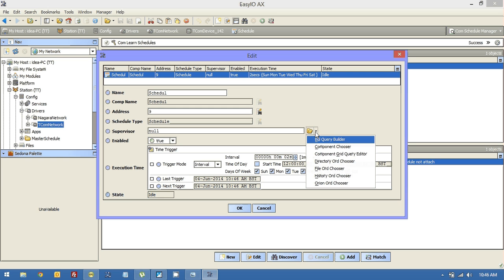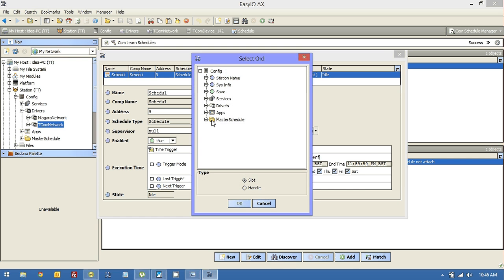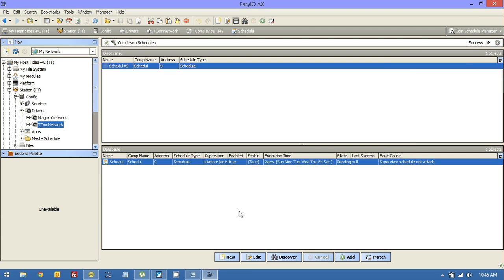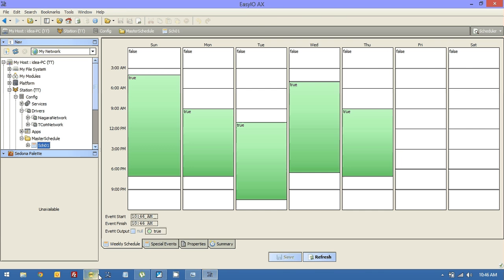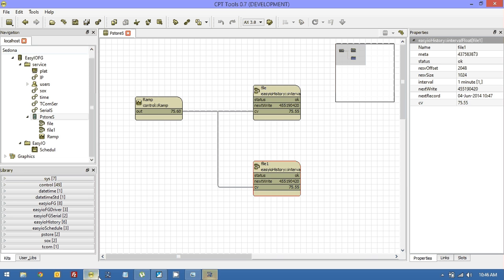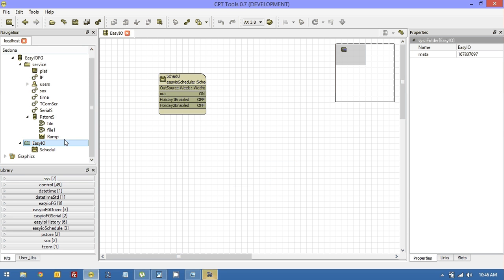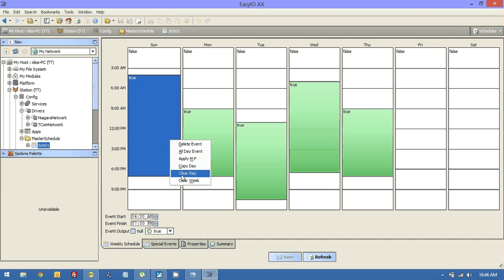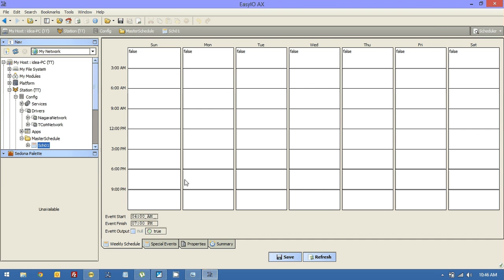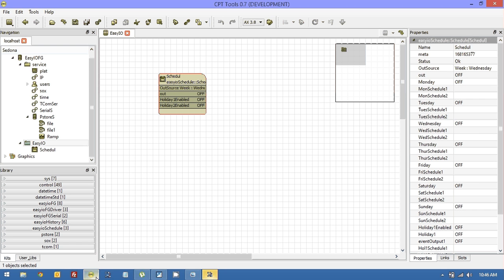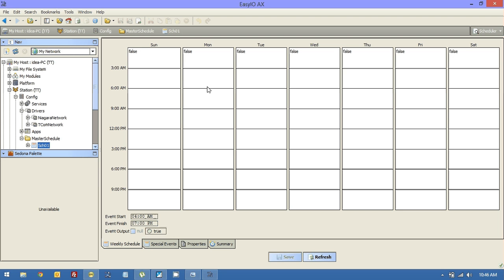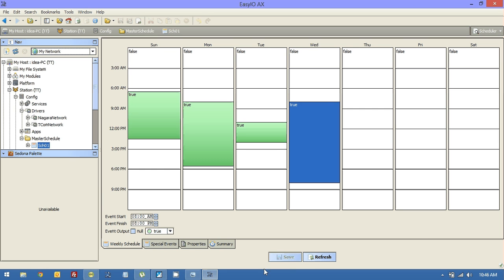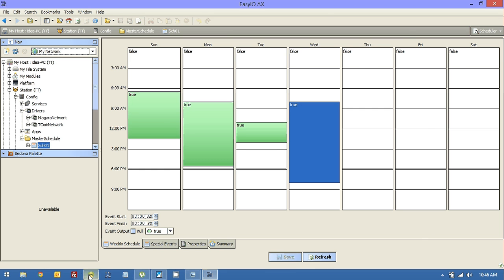If we were to now go into here and say, let's go to our master schedule number one now and link that. Now we're not getting the error. And if we were to look at what that schedule is, you will see we currently have some times in there. And if we go to CPT, go to the schedule, you will see we have times in there now. If I go to here and clear the schedule, save, go back to CPT, you will see the schedule has cleared. Go back and put some in, like so. You will see the schedule comes back, which is really great.